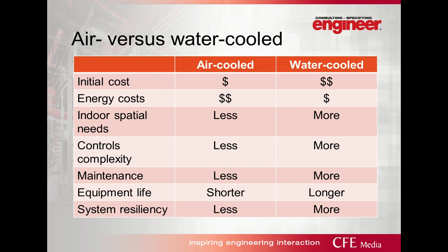On buildings where total energy is a concern — facilities that run 24 hours a day — the energy cost becomes very relevant to the owner. In an air-cooled system you likely need less indoor spatial space, the controls are typically less complex, and maintenance can also be less. However, equipment life is typically longer for water-cooled equipment, and system resiliency can be greater — if you're already investing heavily in a water-cooled system, you will typically see increased resiliency and redundancy placed within the system.